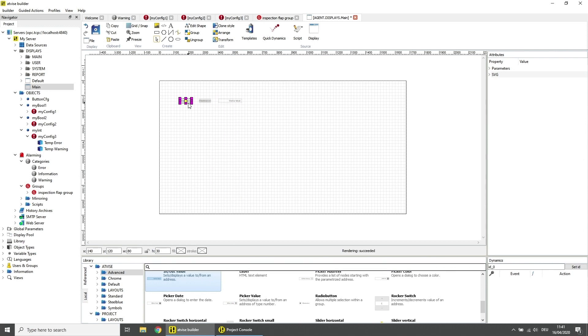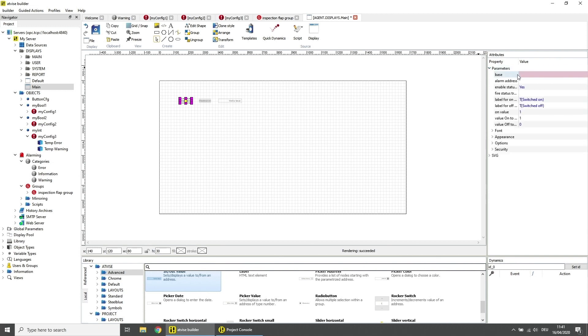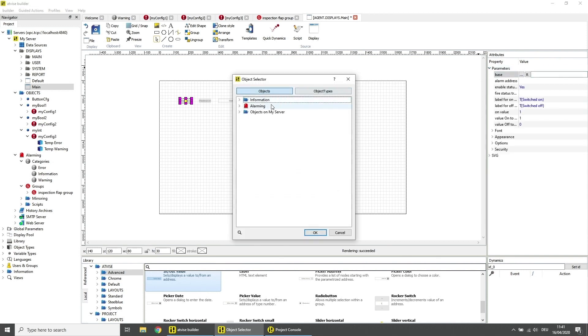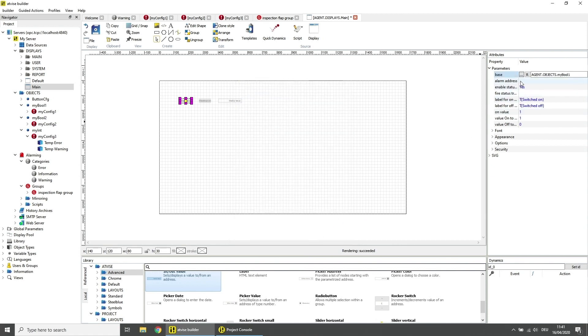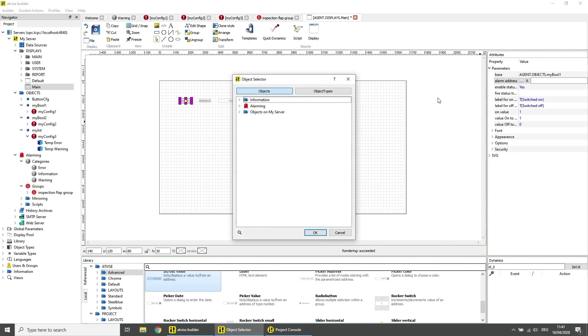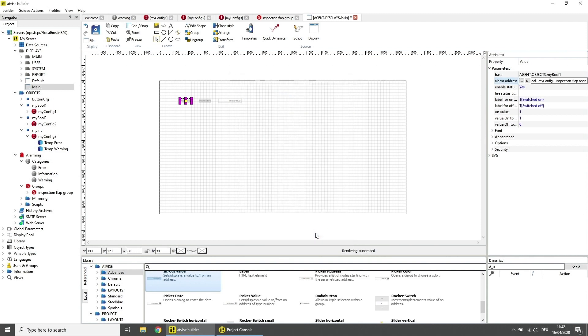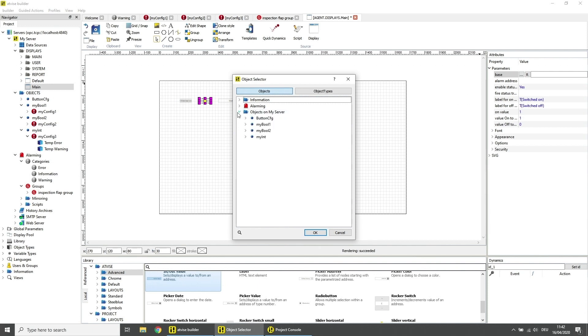Choose the first switch element and set the base parameter to the first boolean data variable. Set the alarm address to the condition at which the switch element should display an alarm. Choose the second switch element and set the base parameter to the second boolean data variable and the alarm address to the corresponding condition.